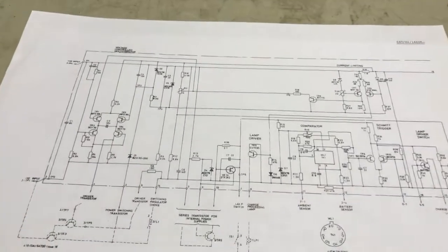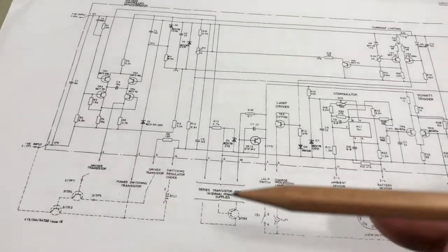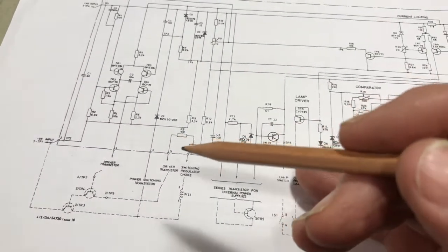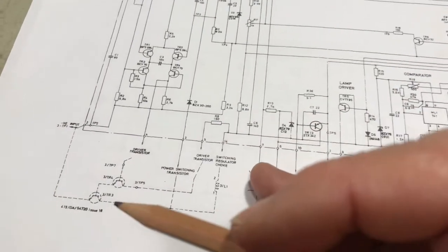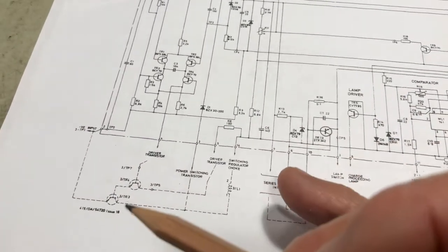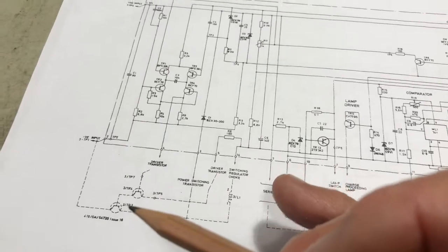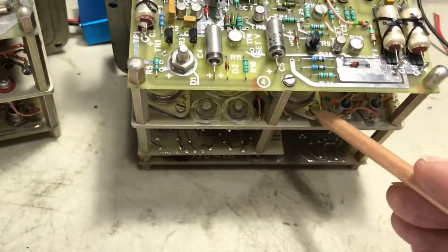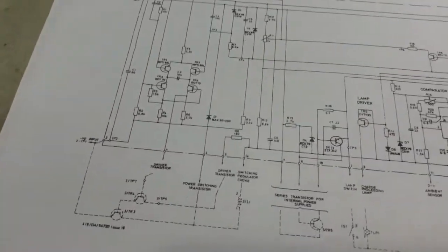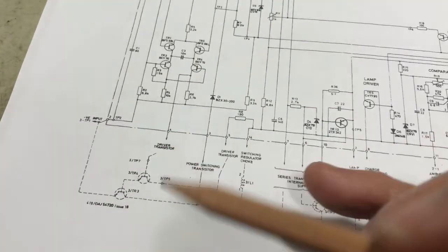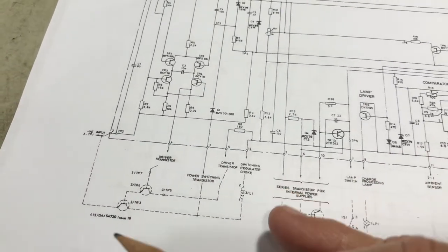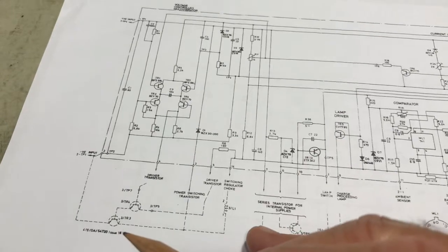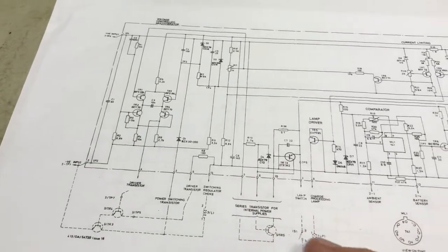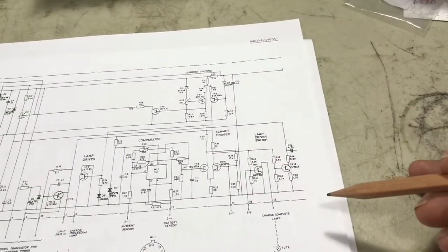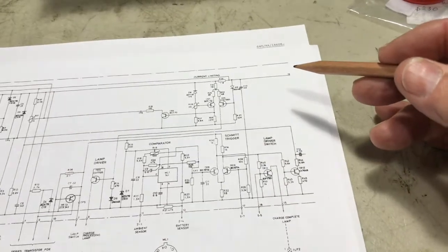Another area, on the actual voltage side of regulation, I've found the main regulator transistor, this one down here, situated on the power section board, fails short circuit. So when it fails short circuit, you're getting maximum voltage out on your batteries all the time, and they're subject to overvoltage.